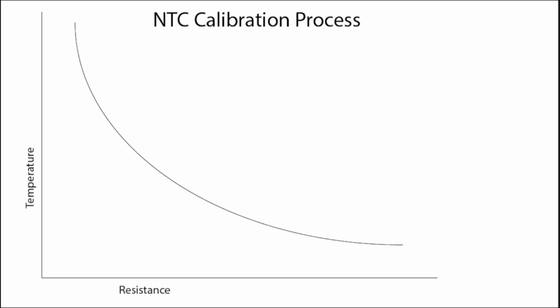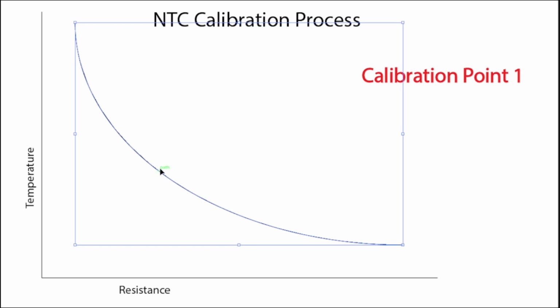So if you do a single point calibration, so let's say if you only put that one calibration point in there, we can't actually calculate the curve shape at all. All we can do is put in an offset. So let's say you do that single point calibration and you work out that the temperature's off by, I don't know, 1 or 2 degrees or something like that. All it can do is shift the curve up or down. So it'll do something like this.